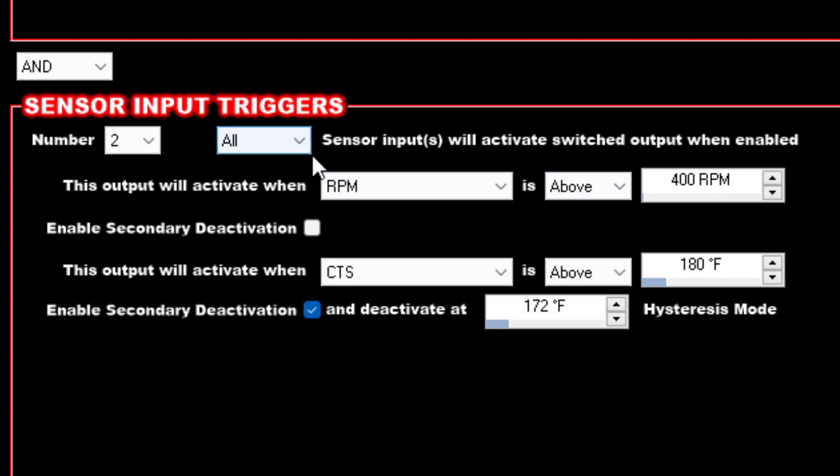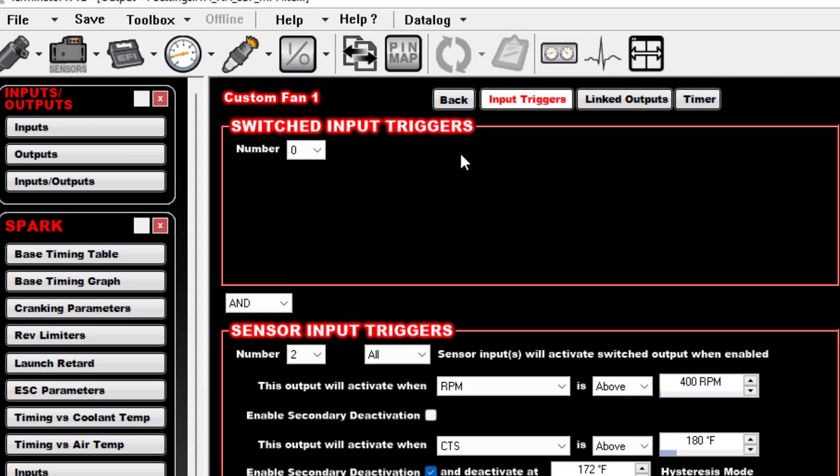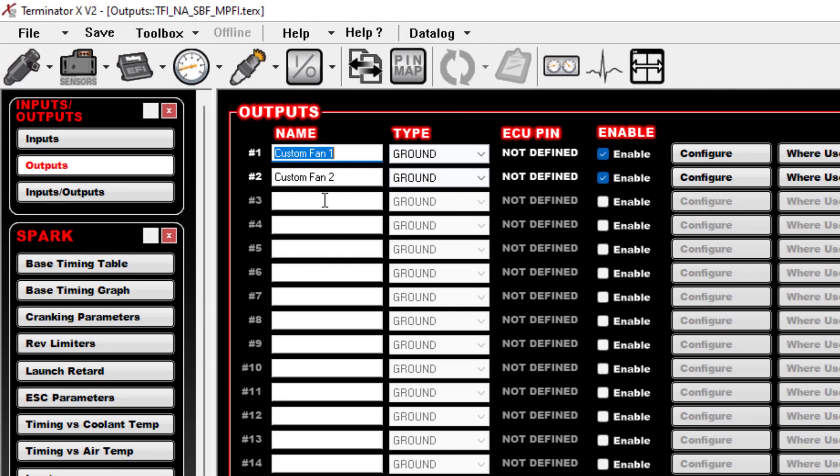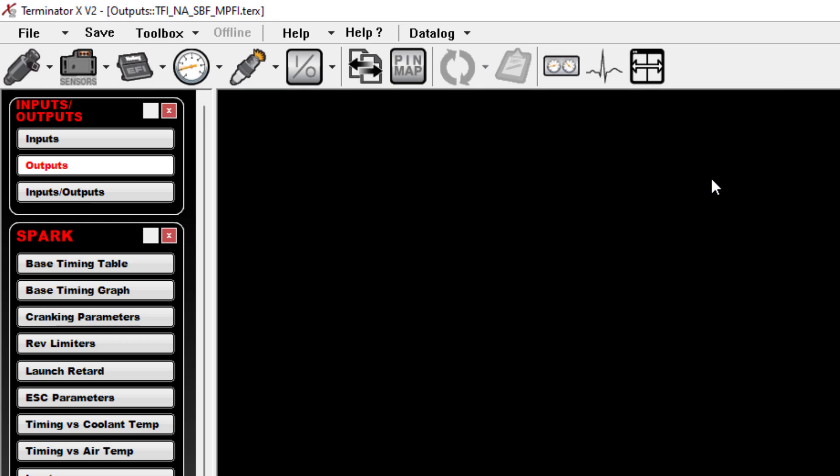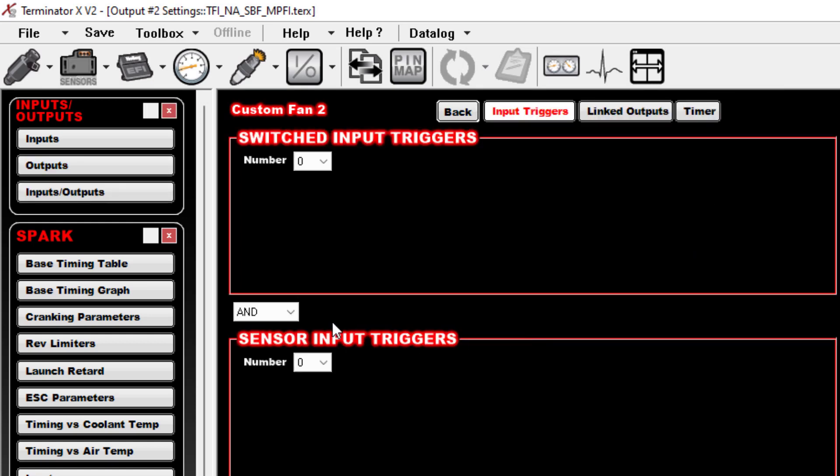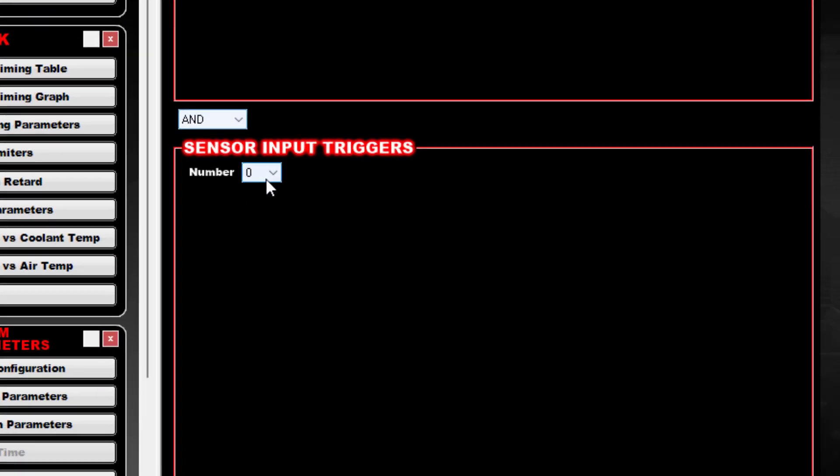This configuration right here will make this fan work the way you want it to for the most part. So that's Fan 1 kicking on at 180, turning back off at 172. We'll go back, we'll go to Custom Fan 2, Configure, do basically the same thing here.